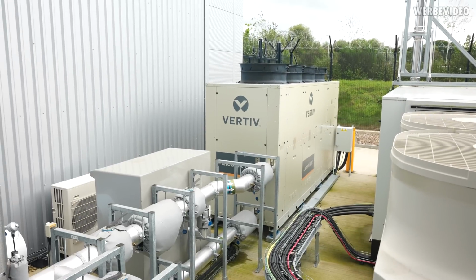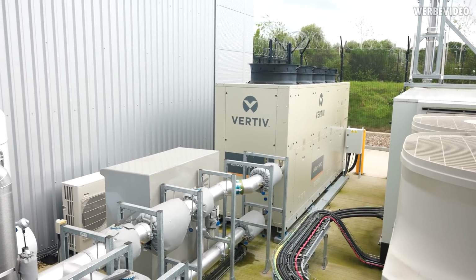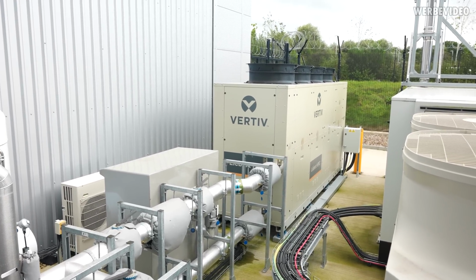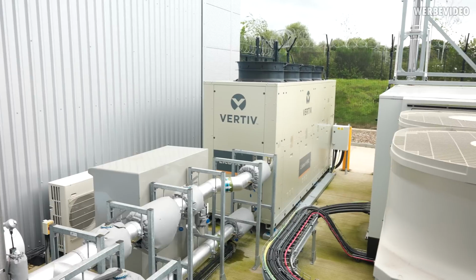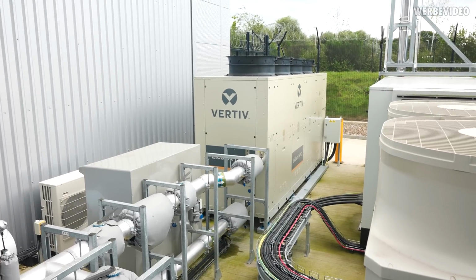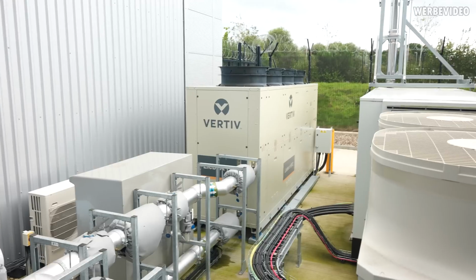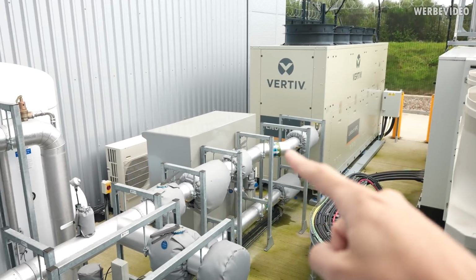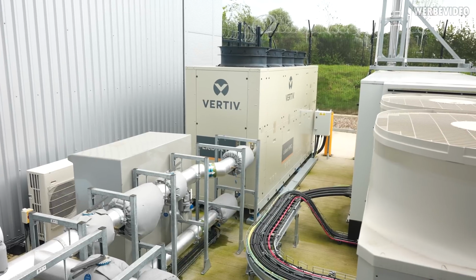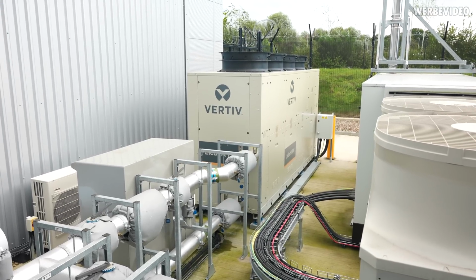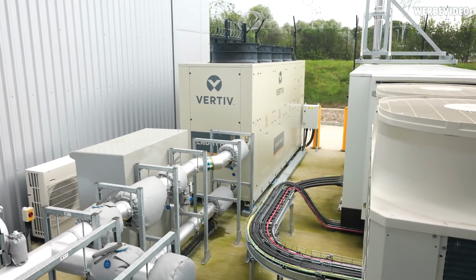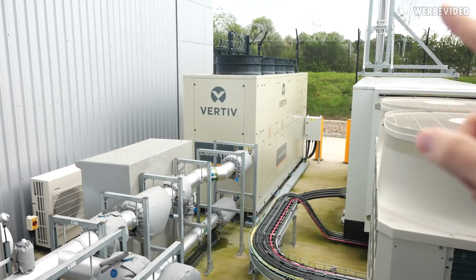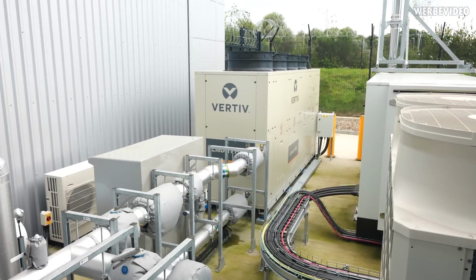Right here we have a chiller responsible for cooling down the water. It depends on the outside temperature whether this runs in free cooling mode or normal chiller mode. Obviously you'd always want free cooling, which means cooling the water directly using the cold ambient air outside. But once that exceeds about 19.5 degrees Celsius, the chillers have to run in normal chiller mode.